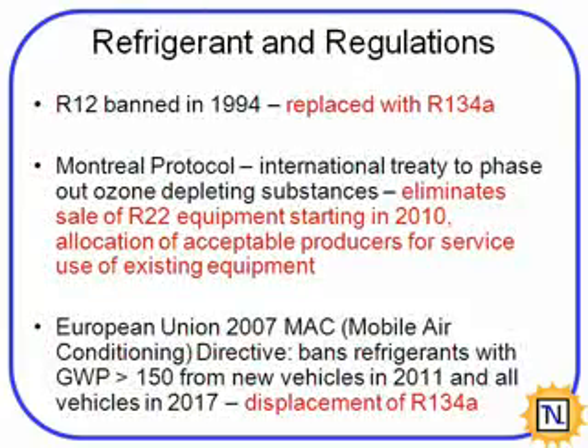And just looking at some of the regulations that have been put in place that are causing these changes. In '94, R12 was banned and replaced with 134A, so you see these in your cars and your refrigerators at home. R22 then, you're starting to see the 410A is really prevalent in your home residential air conditioning systems now as R22 is being phased out. And then the European Union, which is leading a lot of these changes, has a directive that's putting a standard on the GWP that's going to be needed at 150. And as we saw before, all of these are significantly higher than that 150. So our 134A and 410A at some point are going to be phased out. And so that's where then the CO2 and HFO-YF are coming into place.